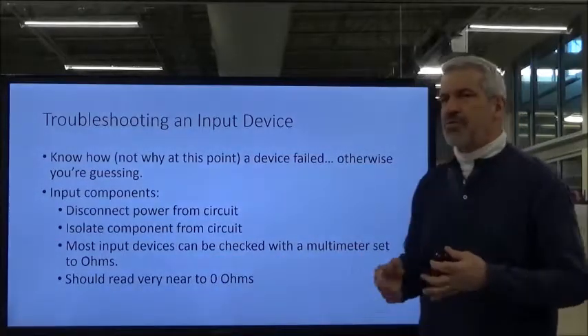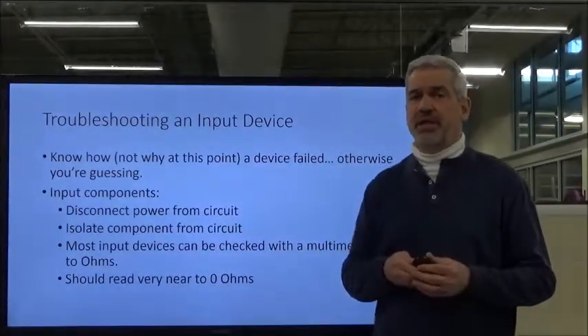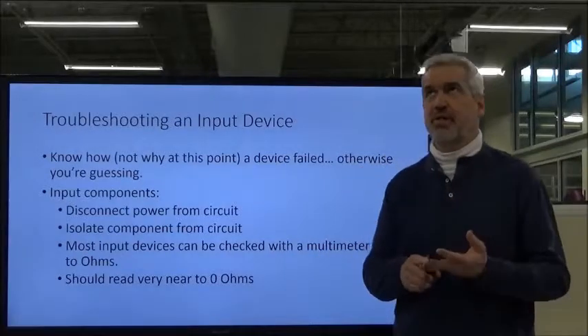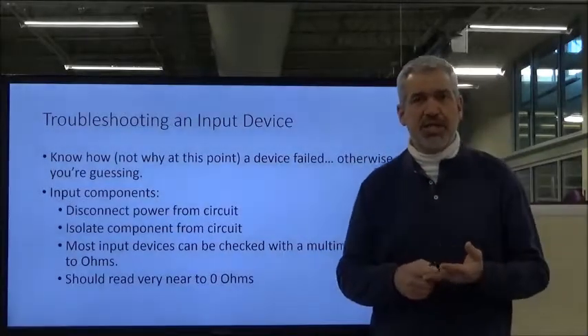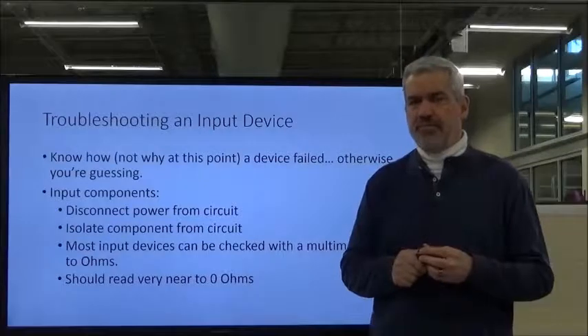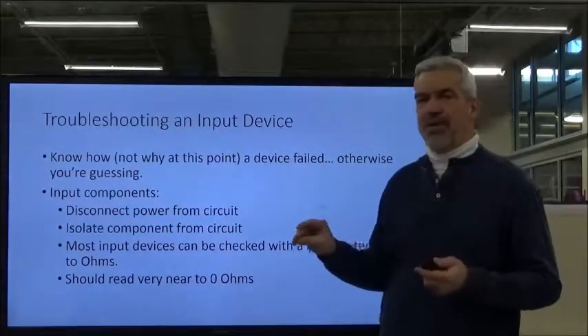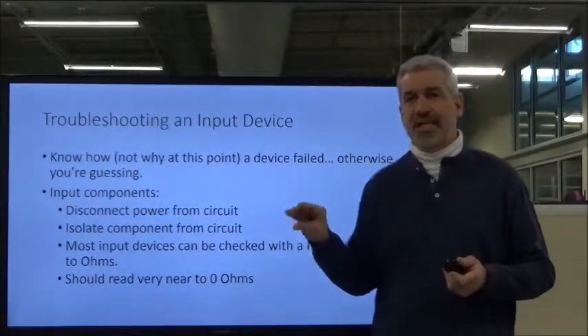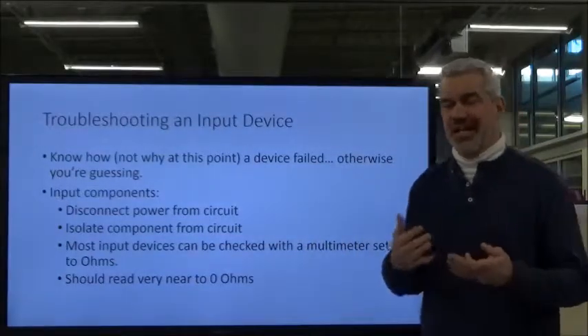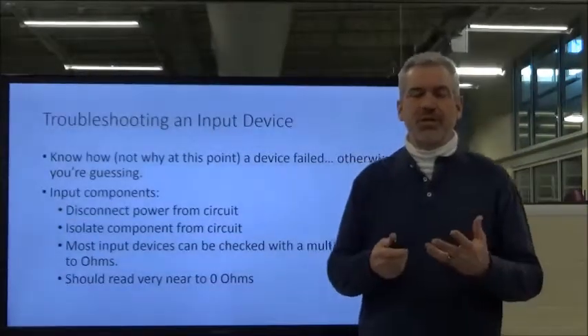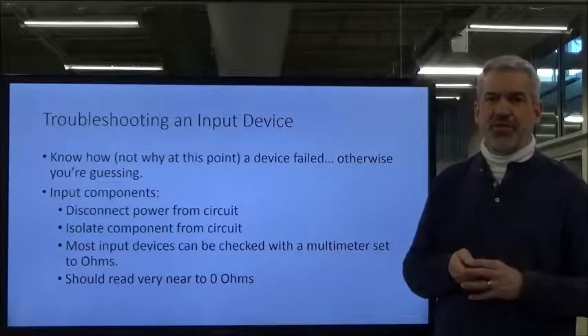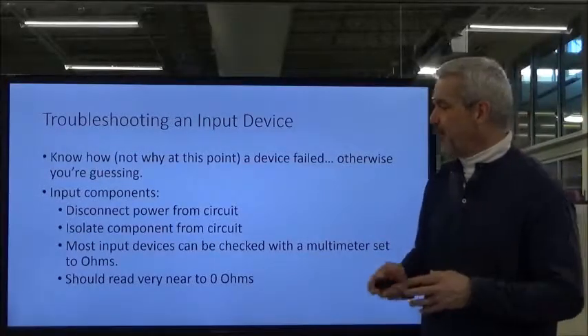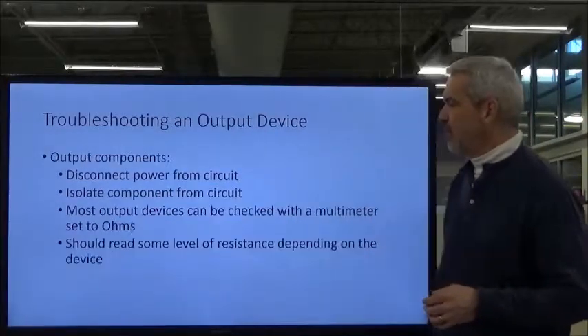Sensors are more difficult, particularly electronic sensors such as photo eyes, proximity switches, and things like that. Those are a little bit different. But for a manually operated or automatic device that just has a set of contacts that opens and closes, you can use a multimeter to check whether that control device is working or not, using the ohm meter.